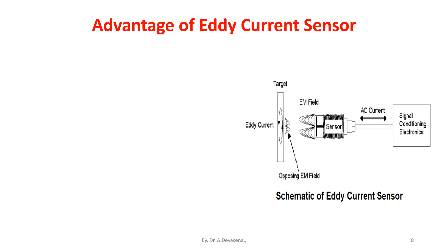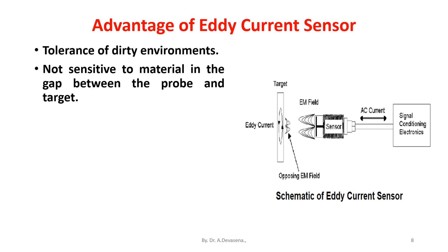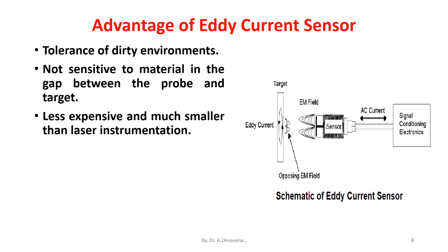Advantages of eddy current sensors: 1. Tolerance of dirty environment. 2. Not sensitive to material in the gap between the probe and target. 3. Less expensive and much smaller than laser interferometers. 4. Less expensive than capacitive sensors.